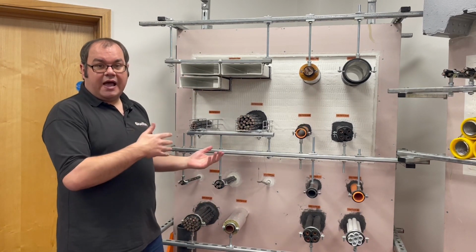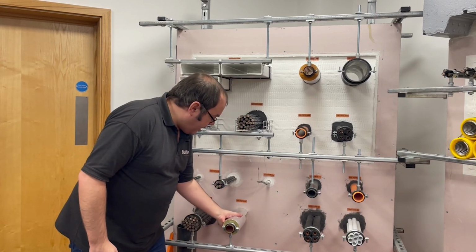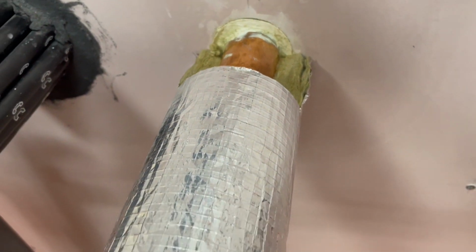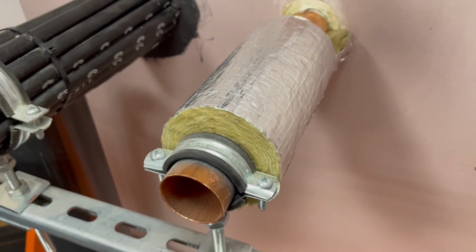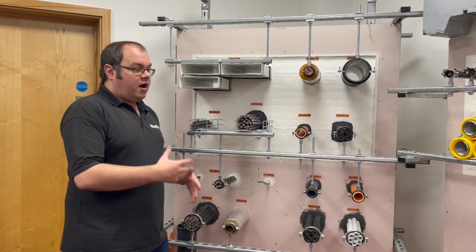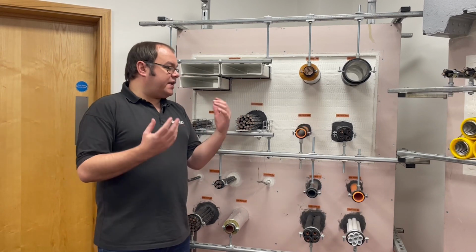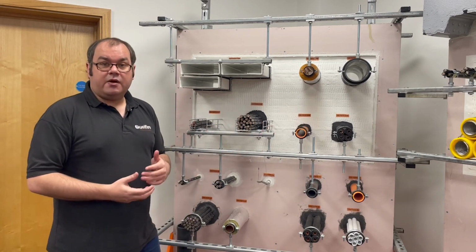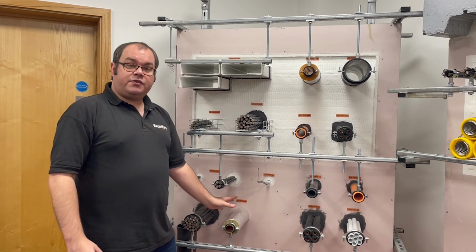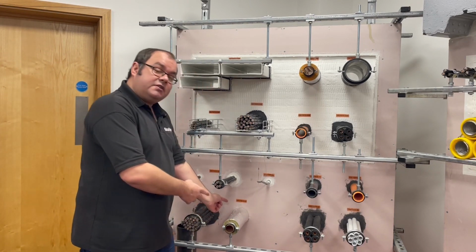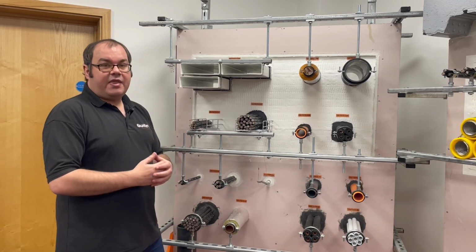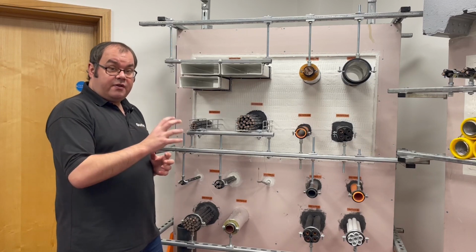Another application we have, showcased down here with this pipe, is what's known as locally interrupted, or LI. So here you have the insulation stop at the penetration, as you can see here, and then it will extend a certain prescribed distance from the face of the wall.